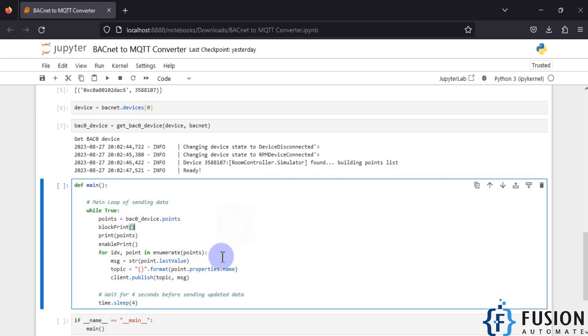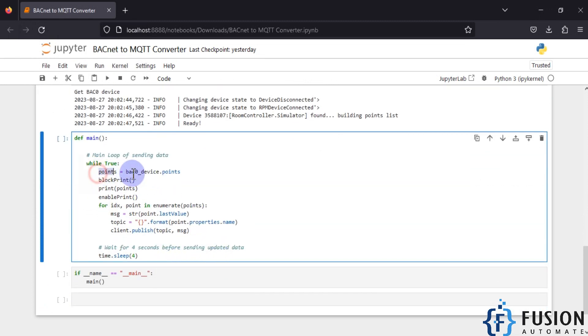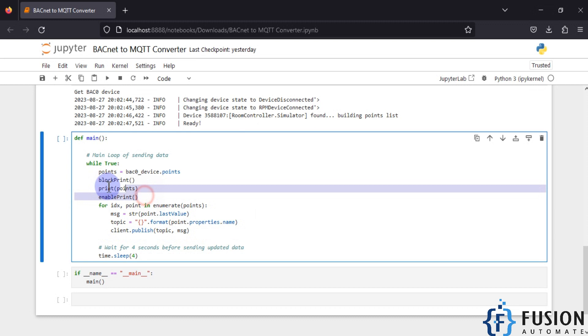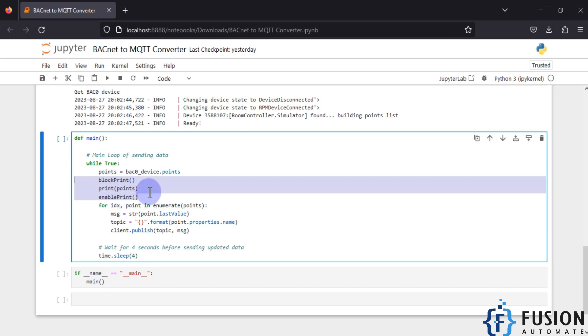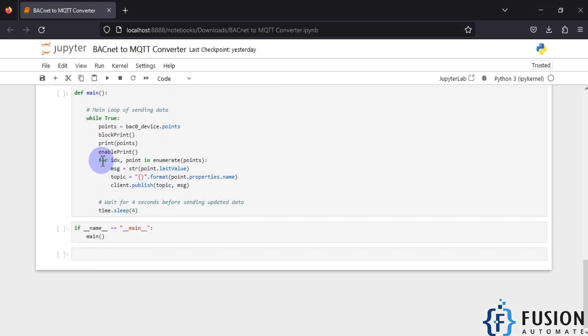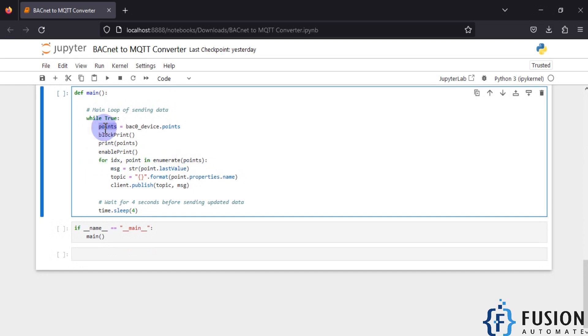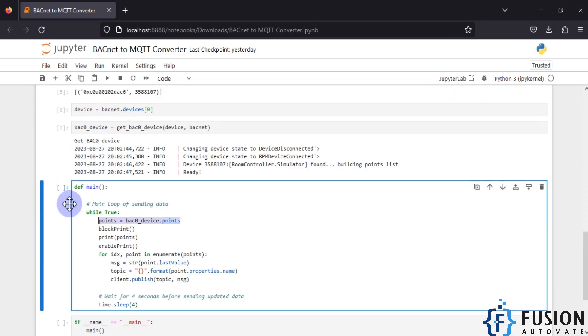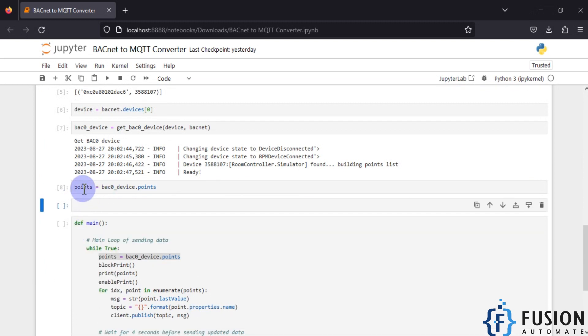This is our main function. It will collect point details from our BACnet device, and for each point it will take the present value of that point, get the properties of that point as a topic, and publish to our Mosquitto broker. You can ignore those adjustment lines — I needed them to make it work properly. From the for loop it gets a point list.